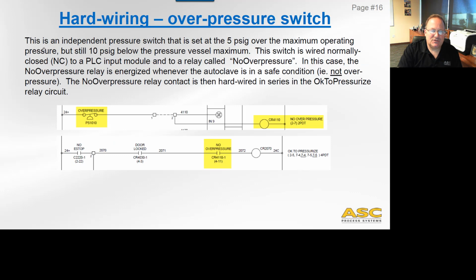The overpressure switch. So this is an independent pressure switch that is usually set 5 psi over the maximum operating pressure of the autoclave, which happens to also still be 10 psi below the pressure vessel maximum, so everything's good there. This is a normally closed switch going to a PLC input module and a relay called no overpressure. So the relay gets energized when there is no overpressure condition. So it's a maintained relay. In this case, the no overpressure relay is energized whenever the autoclave is in a safe condition.